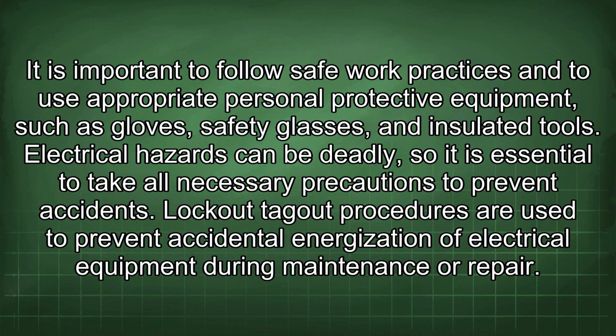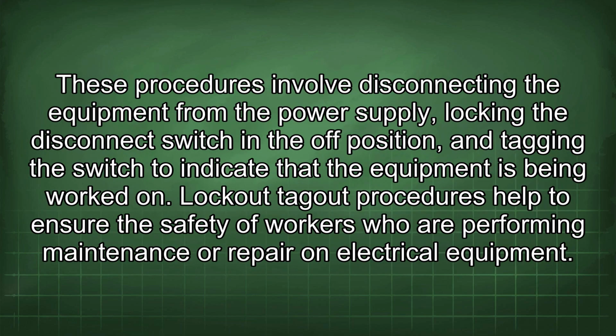Lockout-tagout procedures are used to prevent accidental energization of electrical equipment during maintenance or repair. These procedures involve disconnecting the equipment from the power supply, locking the disconnect switch in the off position, and tagging the switch to indicate that the equipment is being worked on. Lockout-tagout procedures help to ensure the safety of workers who are performing maintenance or repair on electrical equipment.